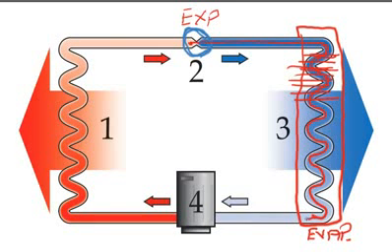and the gas exits this evaporator coil, and it's picked up all of this heat. So it's a gas. This line will feel cold to the touch, but it's a gas and not a liquid. So it's entering the compressor, and basically a compressor is either a piston type pump or some type of a scroll positive displacement pump. And so many times you'll hear this copper line referred to as the suction line, because it's going into the suction side of the compressor or pump.